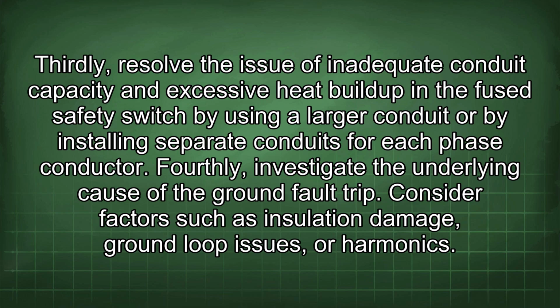Thirdly, resolve the issue of inadequate conduit capacity and excessive heat buildup in the fused safety switch by using a larger conduit or by installing separate conduits for each phase conductor. Fourthly, investigate the underlying cause of the ground fault trip. Consider factors such as insulation damage, ground loop issues, or harmonics.